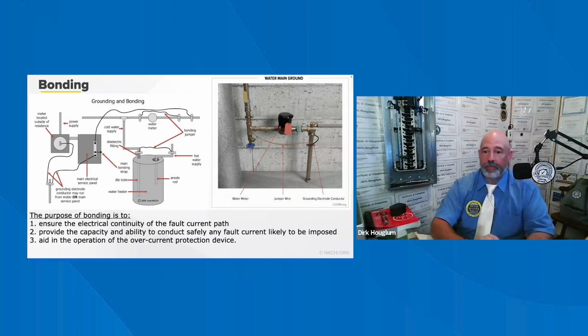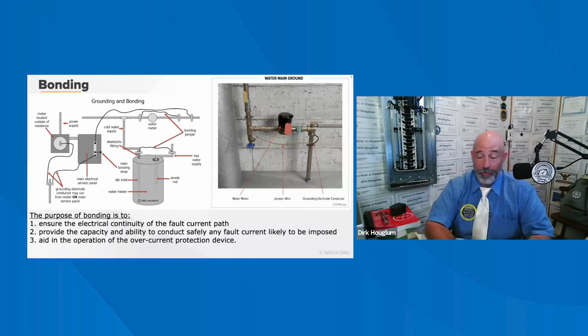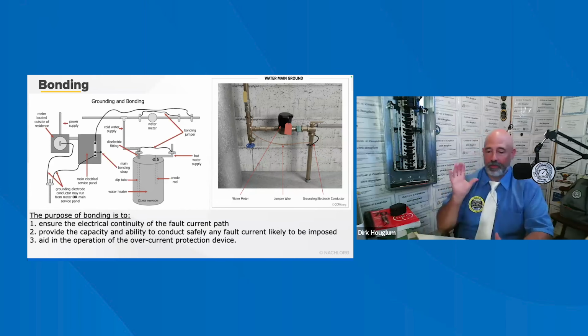We bond pipes because if a metal pipe is energized inadvertently, a bonding jumper provides the easy path back to trip the breaker. Refer to the following illustration of the grounding electrode conductor connected to the metal water pipe near the water meter. Okay. Inspectors may observe metal water lines bonded at the water heater supply pipe and metal gas pipe that are so close to the panel board.